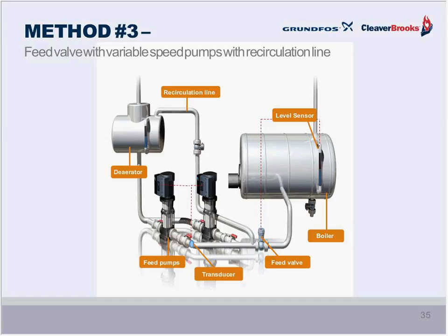Now, notice that neither the sensor nor the feed valve is sending an electronic signal to the feed pump controller in the drive. Instead, there's another method for doing that with a transducer that's located between the pump and the feed valve, and that sensing of pressure change is what provides the impetus for varying the motor speed. The signal goes to the drive and causes the pump and motor to speed up or slow down to meet those changes in flow requirements while trying to maintain a constant pressure. And we're going to use this control method for one of our selection exercises in today's webinar.